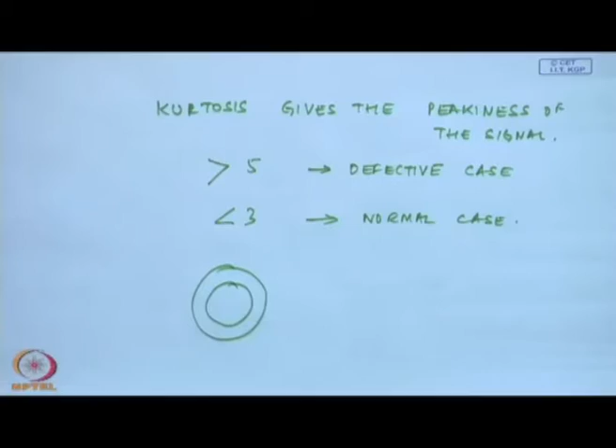Because if these bearing faults go unnoticed, for example, a crack in a bearing outer race, we are going to have problems. The bearings are going to fail. And I will tell you in other case studies, many times, particularly in electrical motors, there is electrical conductance occurring through the bearings, because the shafts are carrying rotors and there is a lot of magnetic flux, and this flux gives rise to small ground voltages. At the bearings, because of the oil film, very significant sparking occurs.